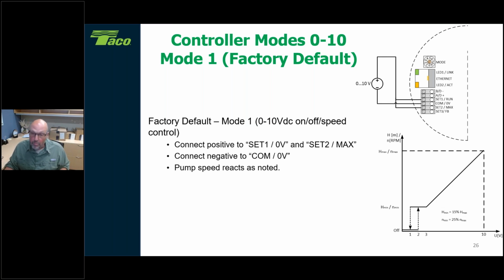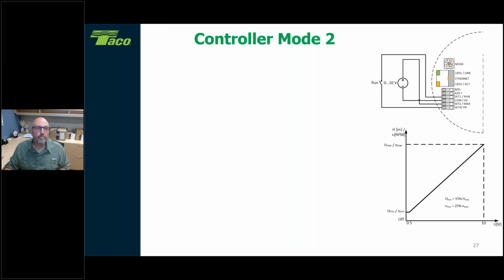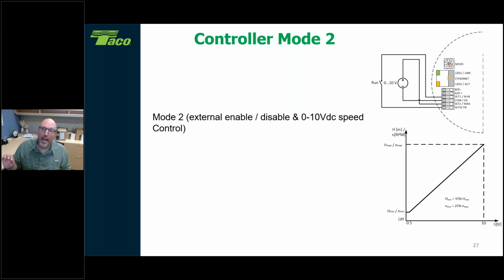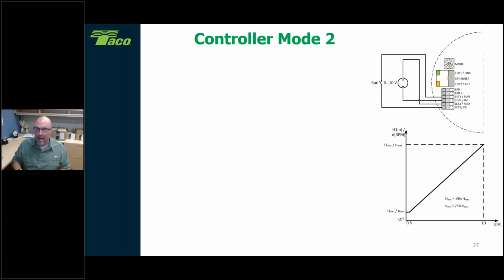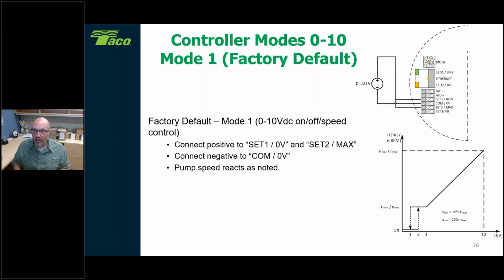Okay. So that's the simple wiring that's going to come into the circulator itself. In mode 2 now, you're going to have also an on-off switch, because we had an on-off before. I'll come back to mode 1 for a second. We go down to 0. Once we get below 1 volt, the circulator shuts off. So we do have a mode here to tell the pump to stop running.